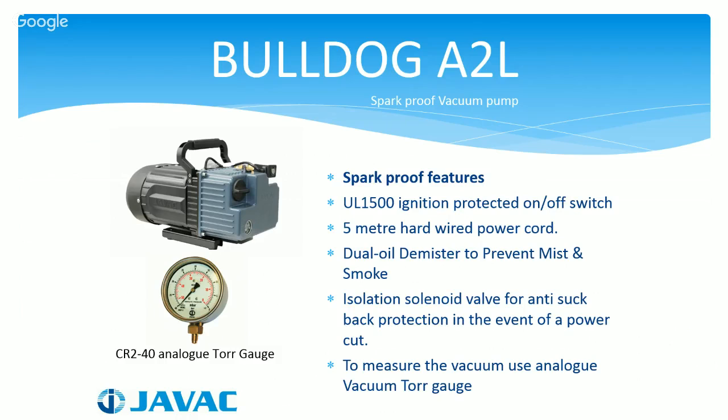When evacuating, we would also strongly suggest that the system is purged with OFN before evacuation. This is just to rid the system of any dormant gas. This would avoid any unnecessary compression of the refrigerant.